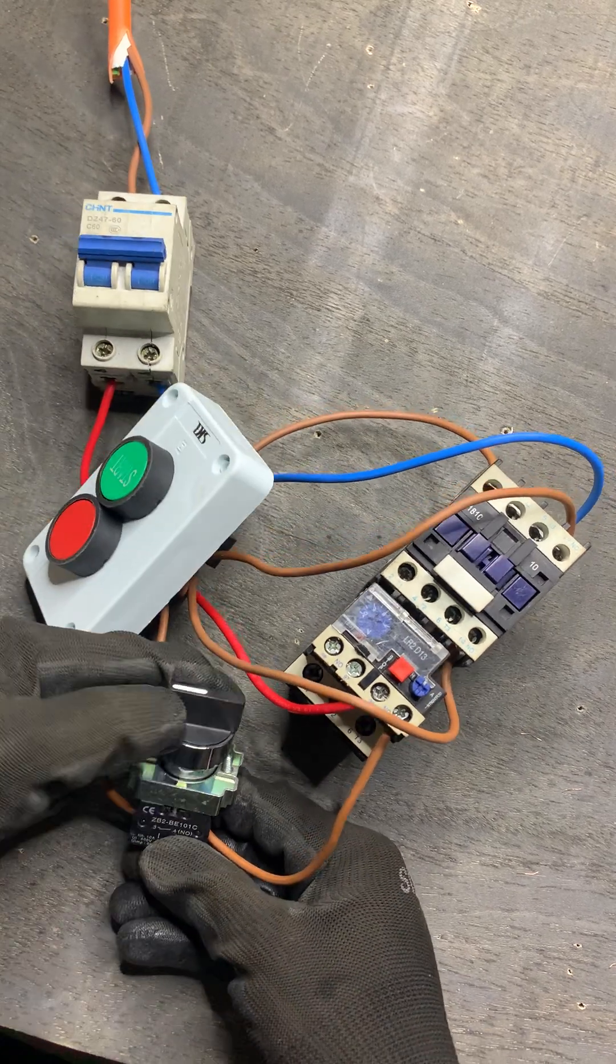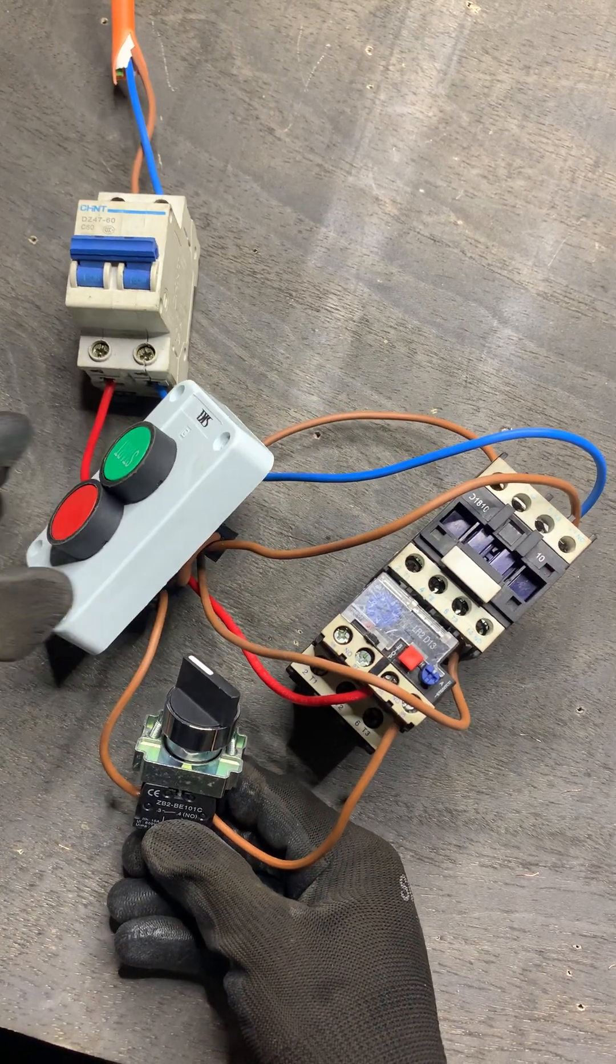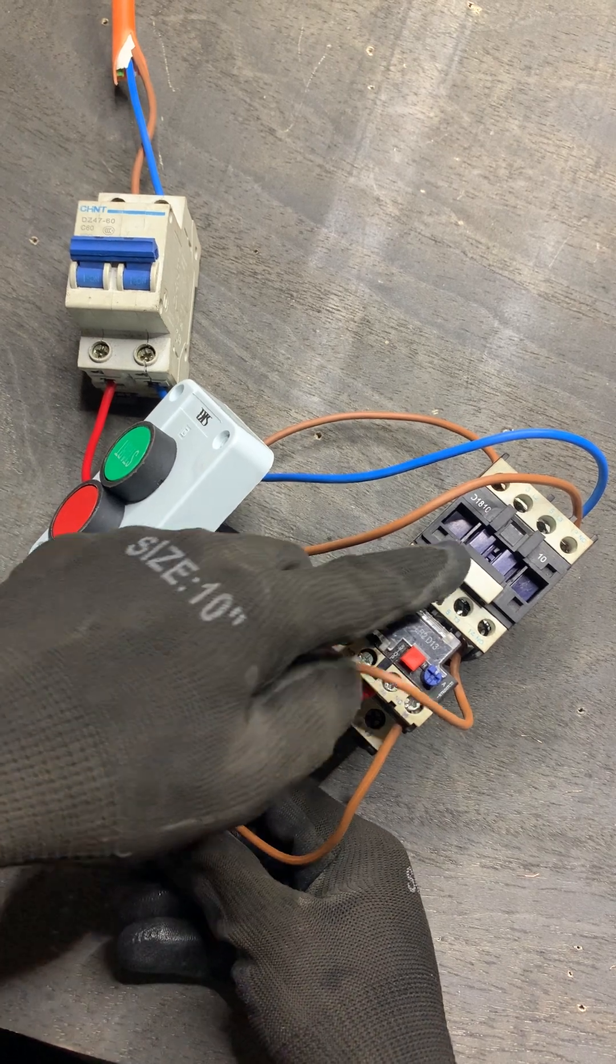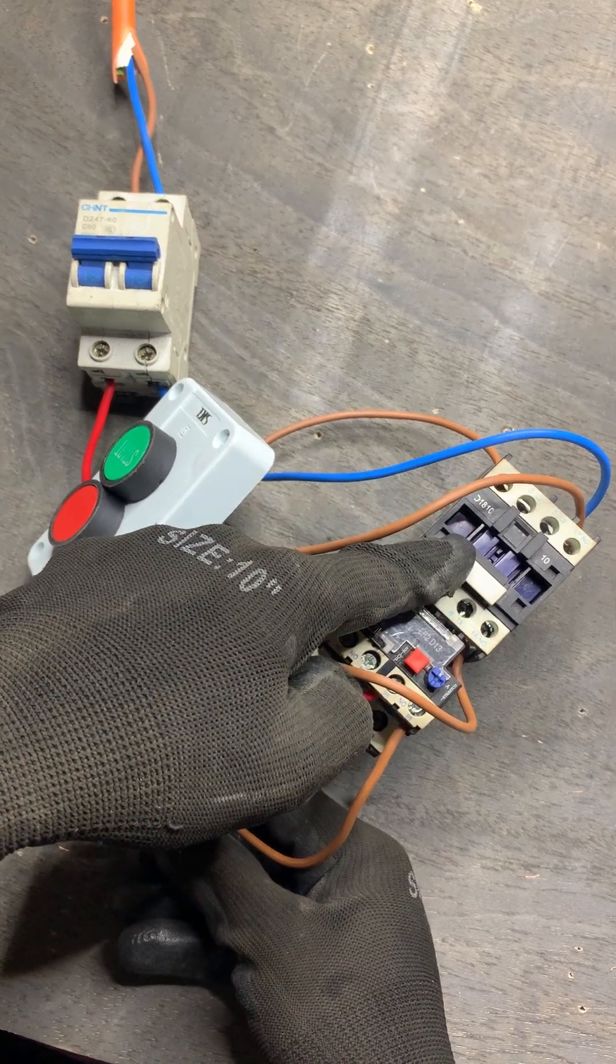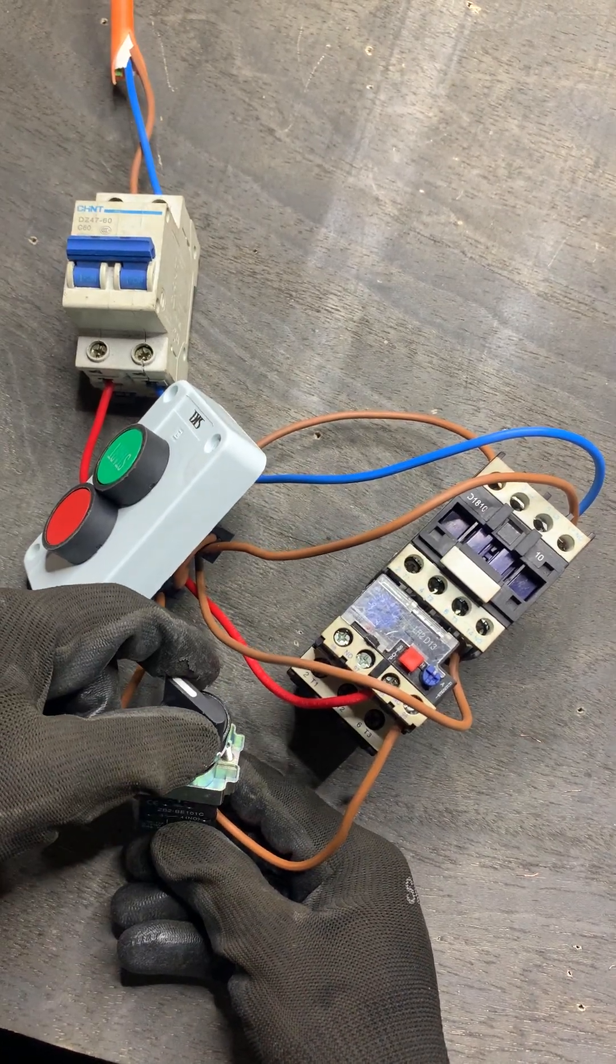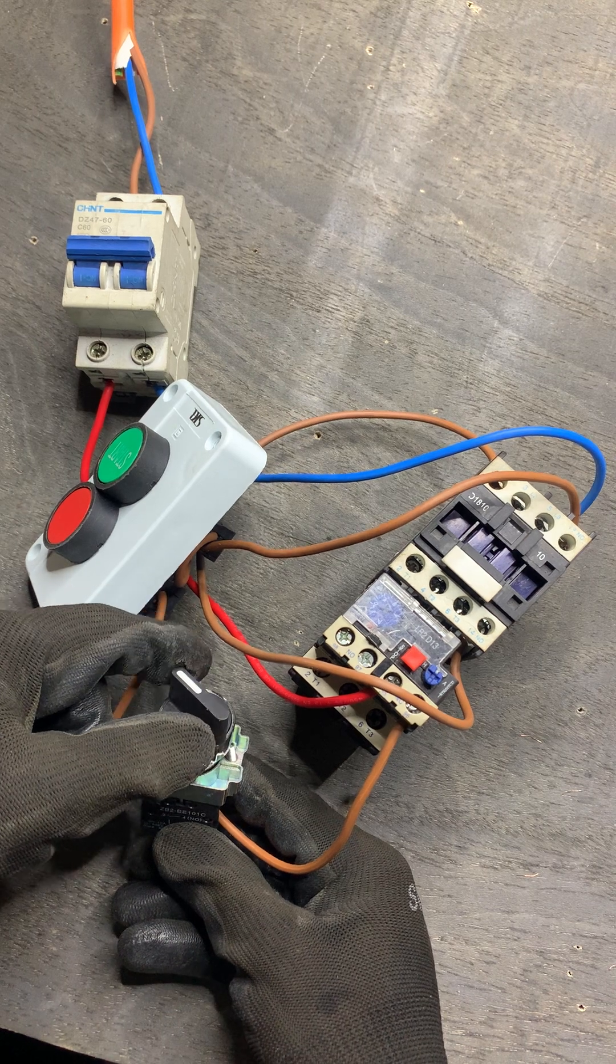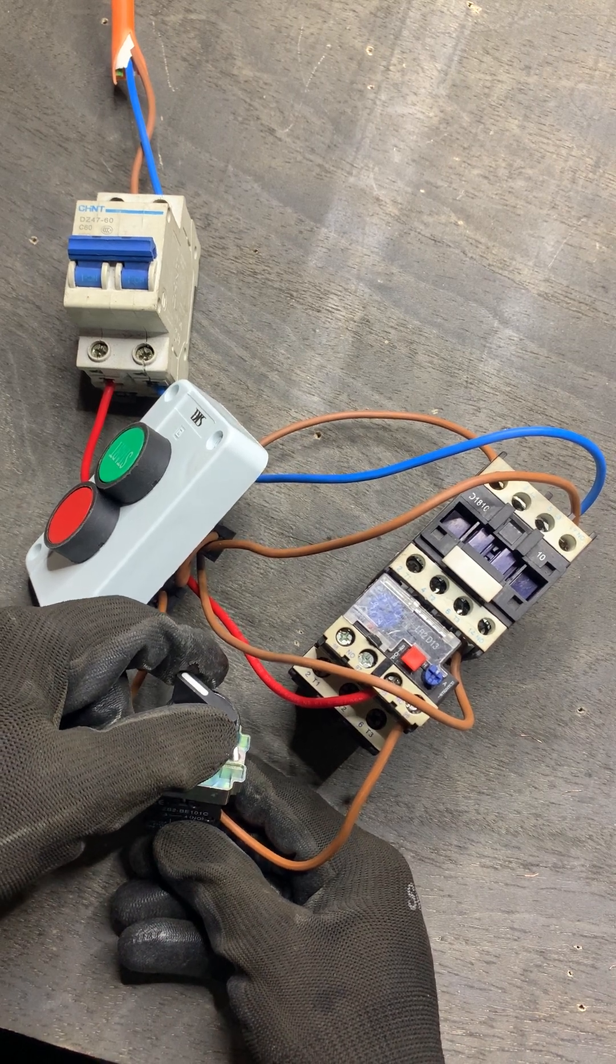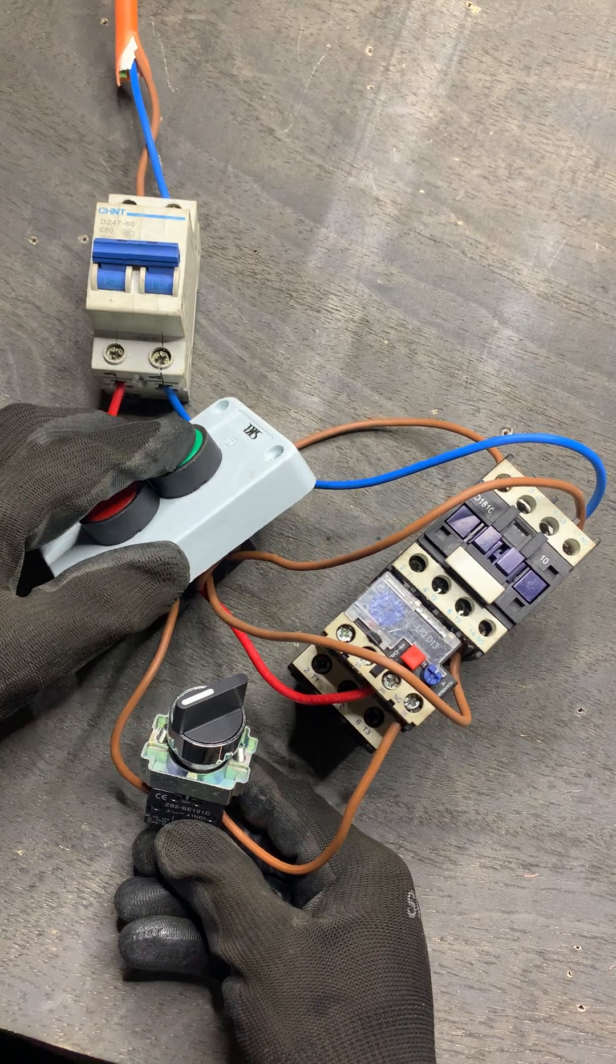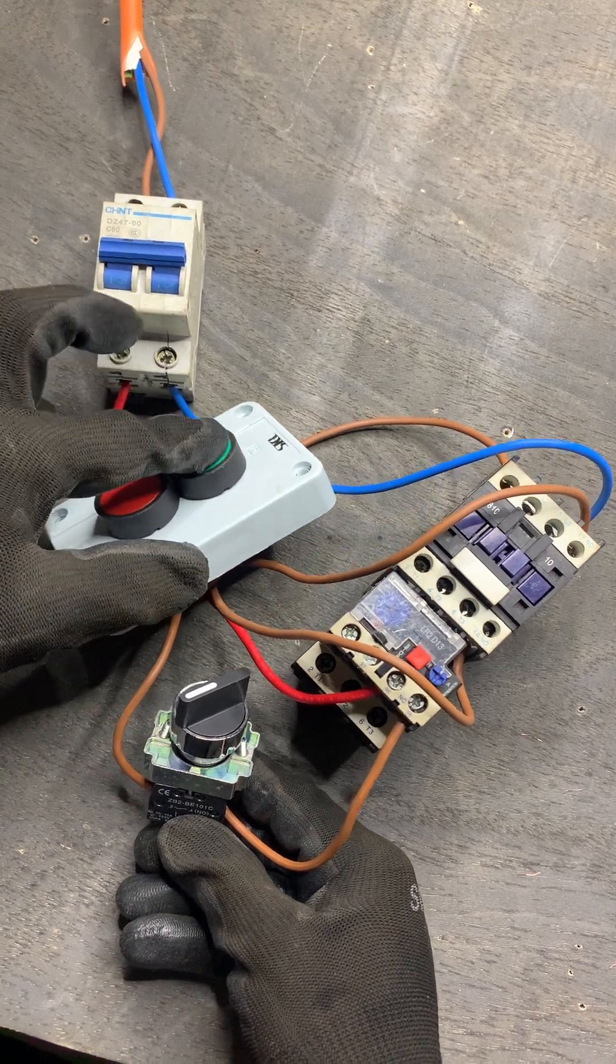When I press on the start button, you can see the contactor has energized. So I will just rotate the selector switch - you see it will go off instantly. And then when I'm pressing on the start button it will not work.